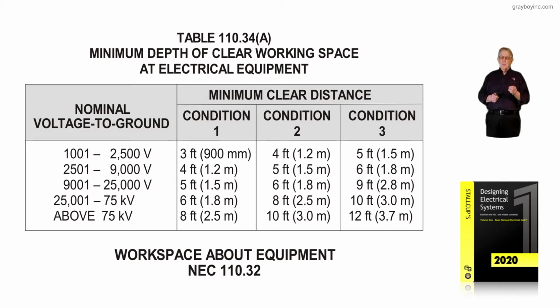So again, a recap, a reminder: condition 1 is where an insulated wall is behind the worker. Condition 2 is a grounded wall. And condition 3 is equipment opposite equipment. Now we have 5 voltage levels listed. Over 1,000 volts to 2,500 volts, you can see it's a 3-foot clearance for condition 1, condition 2 is 4, and condition 3 is 5.